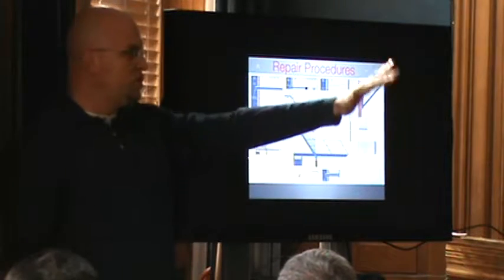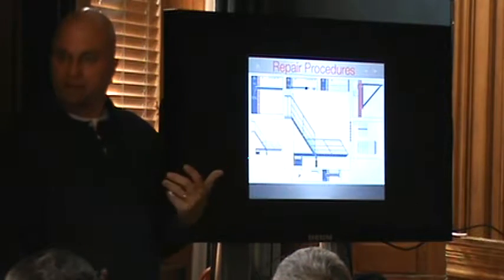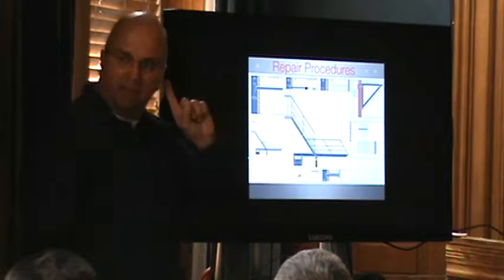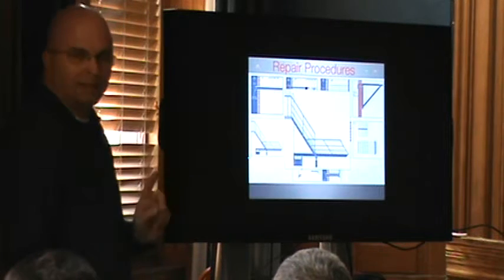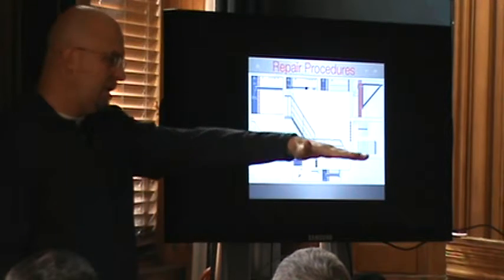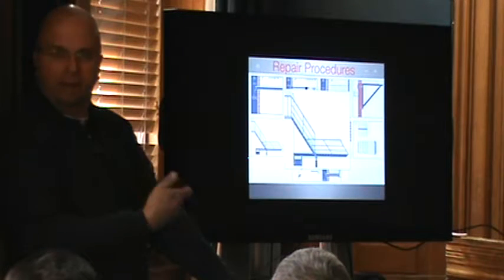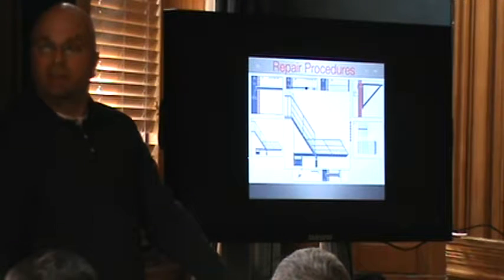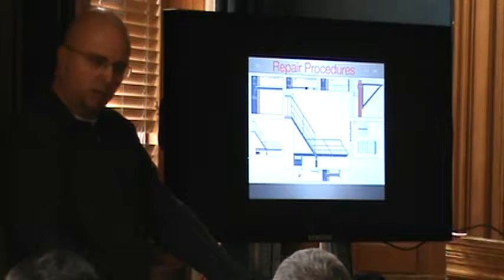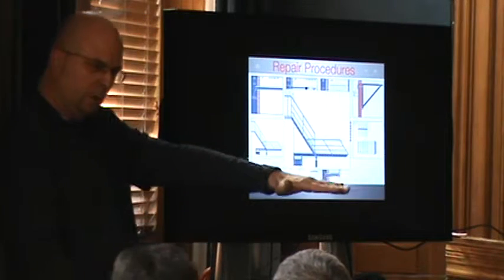What's the norm when snow comes and pigeons land on it, does it drop? Yes. A properly weighted fire escape with no release arm, you're supposed to come here, step on the first tread, and activate it. It is so perfectly balanced like a Swiss watch that when you step on it, it starts dropping 2 to 3 feet per second, hits the ground and stays down, and then you self-evacuate, and when the firemen arrive, they use the same fire escape to get into the building, if they need it. That's how it's supposed to be. It's a Swiss watch. Doesn't always work, but it's a Swiss watch.